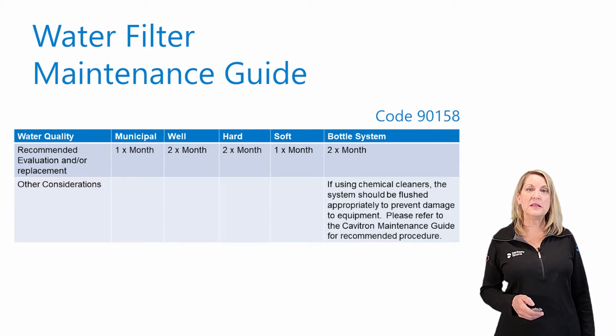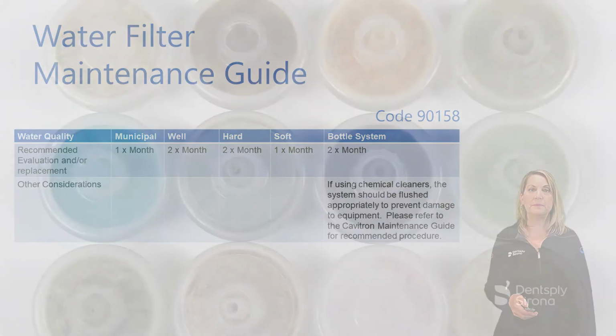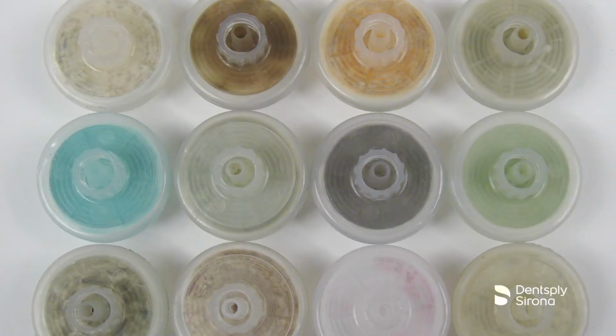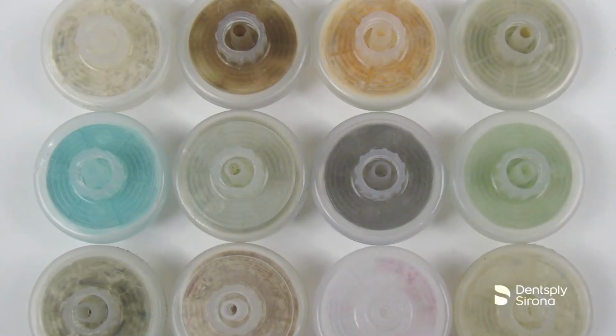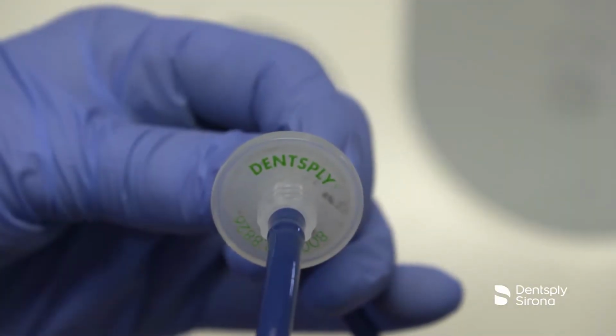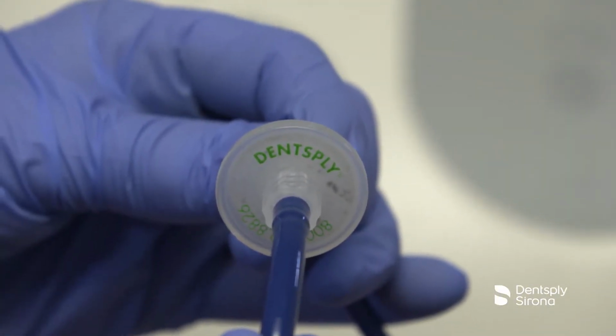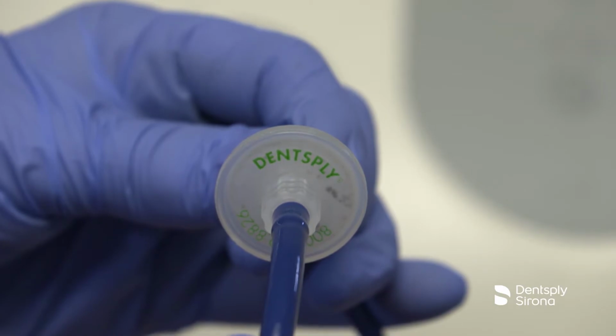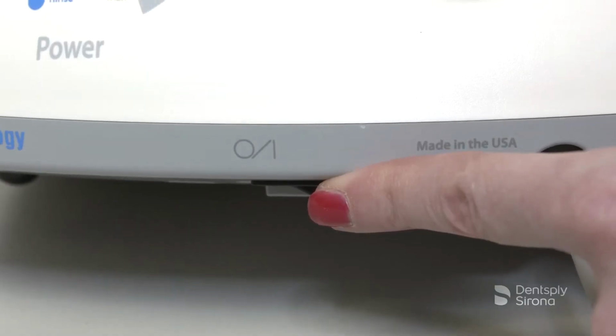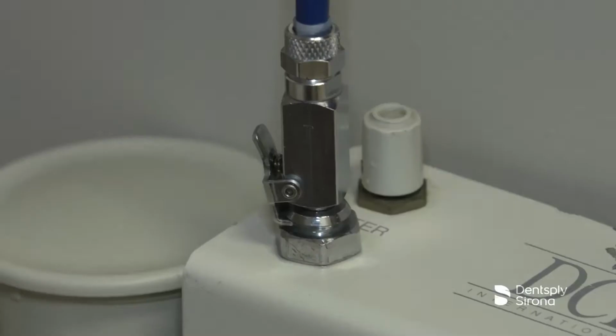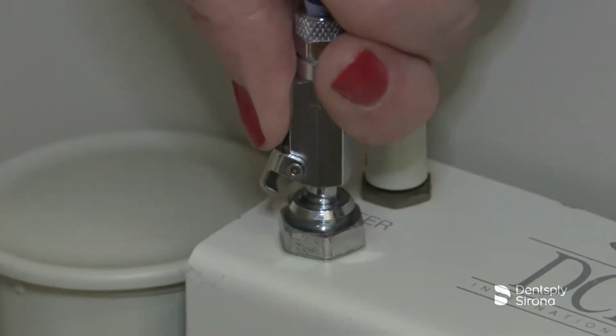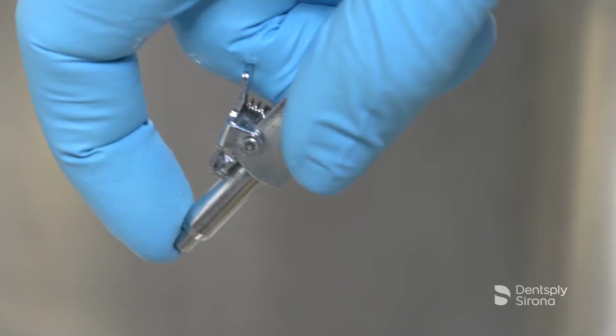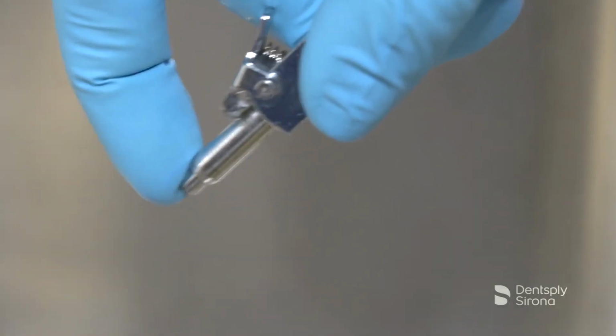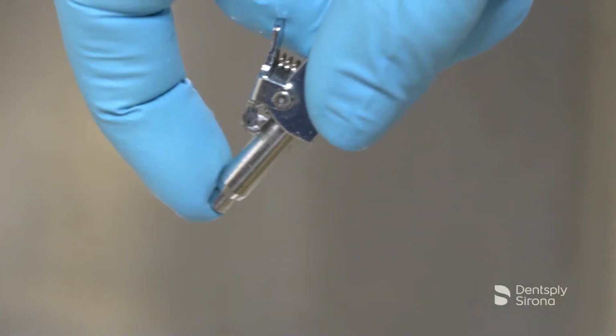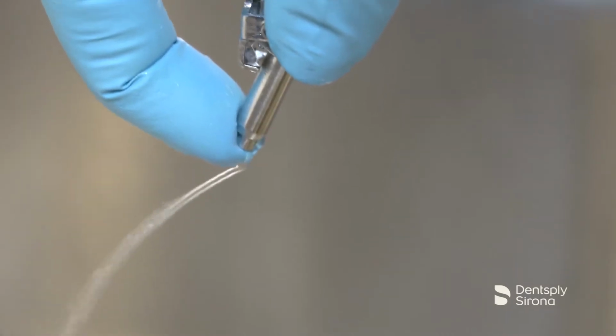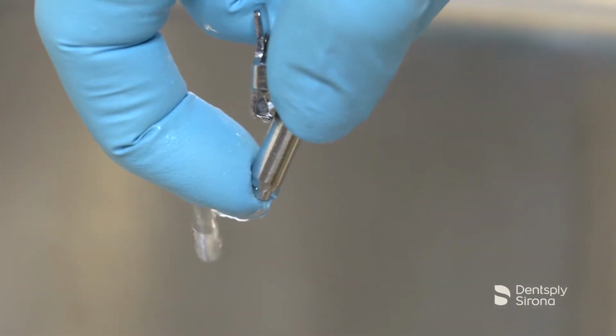Next, you will see the procedure on how to do this. When the waterline filter becomes discolored, the filter should be replaced to prevent reduced water flow to the Cavitron Plus system. This should be checked and/or replaced monthly. To change the water filter, begin by verifying that the system is turned off. Disconnect the water supply hose from the dental office water supply. If a quick disconnect connector is attached to the end of the hose, relieve the water pressure by pressing the tip of the connector in an appropriate container and drain the water.